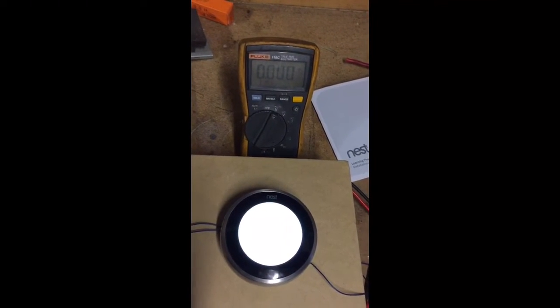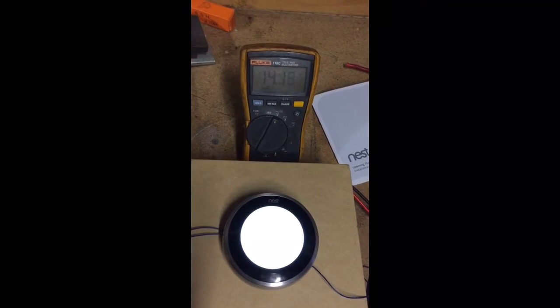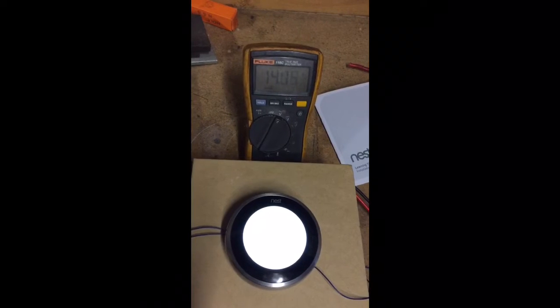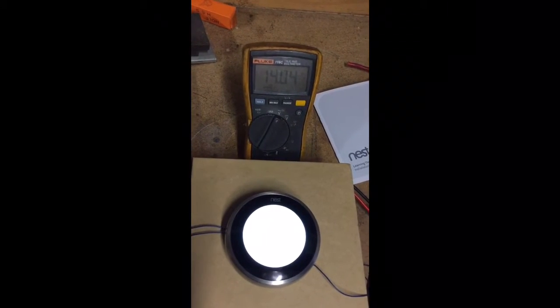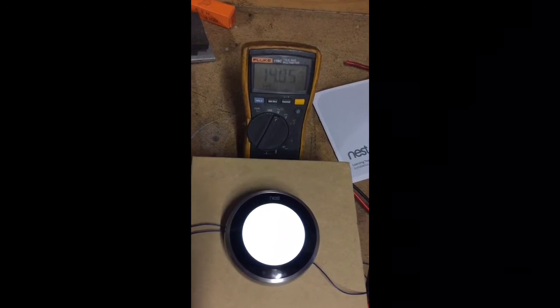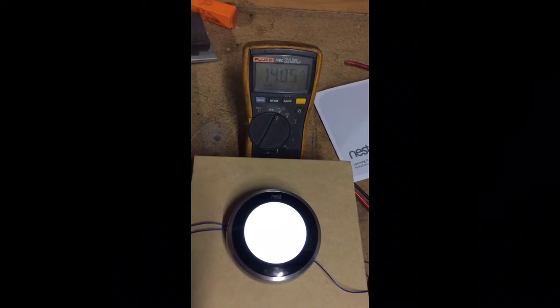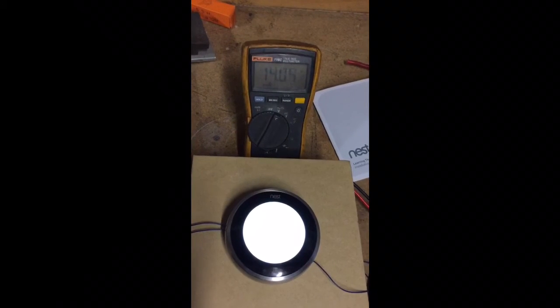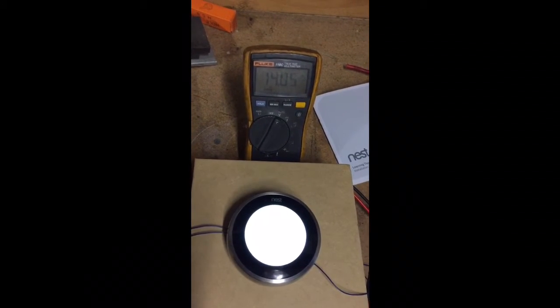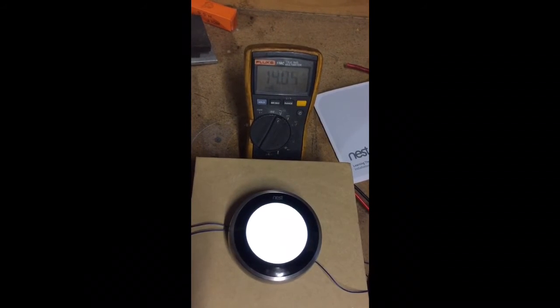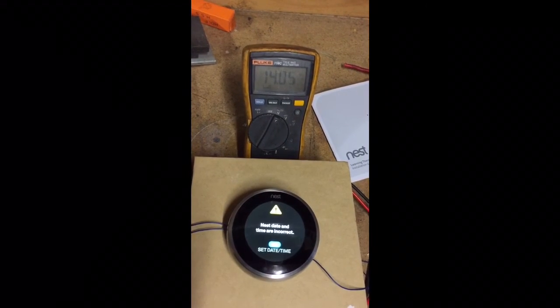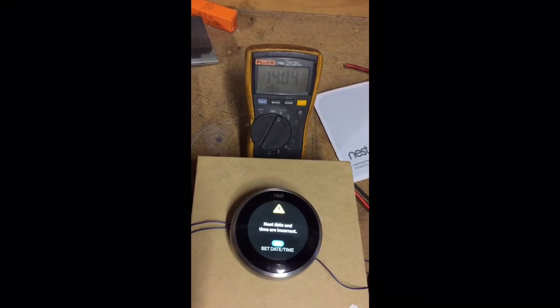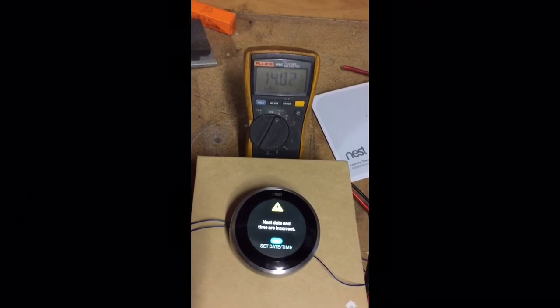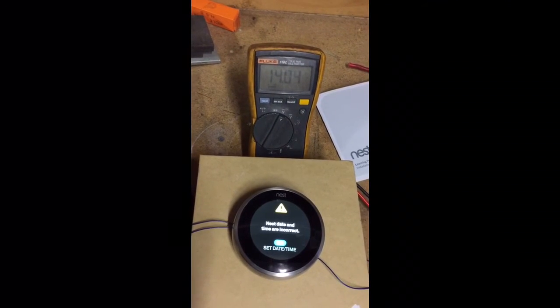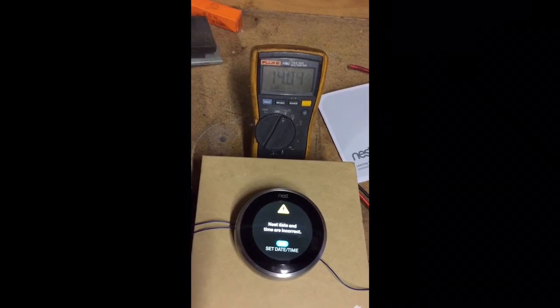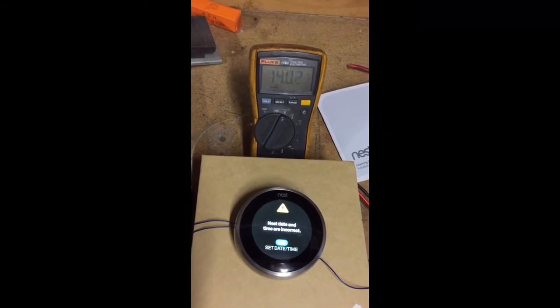Okay, so just about to fire up the controller now. You'll see that the LED above the Nest logo is flashing to indicate searching for the network. We haven't got that set up at this stage. We're just going to worry about the bench testing configuration. As you can see on the multimeter there, even though we've got no call for heating, we've still got a residual output of 14 volts. Now, I think that's just due to the solid state internals in the Nest controller, and once we get a load on there like a gas valve or something like that inside the heater, that'll come down nice and quick. You can see it's starting to drop away now quite slowly.